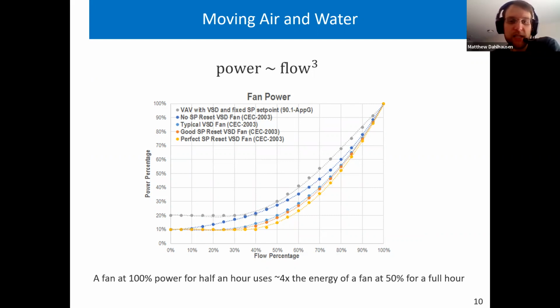Given that the amount of air needed to provide heating or cooling is usually more than needed for ventilation, it can be expensive in terms of fan energy to meet heating or cooling loads with air-based systems.